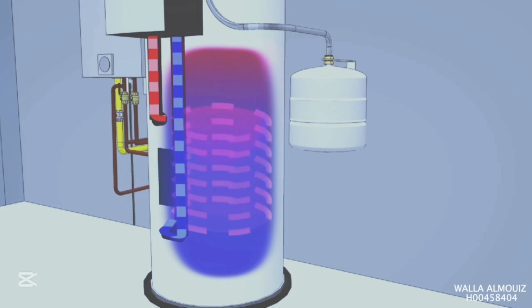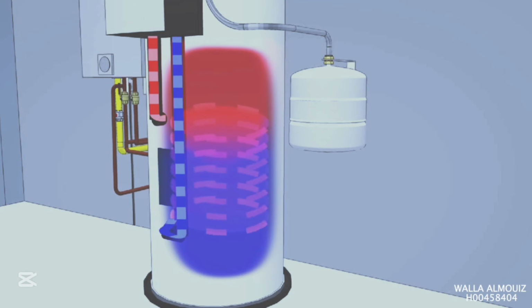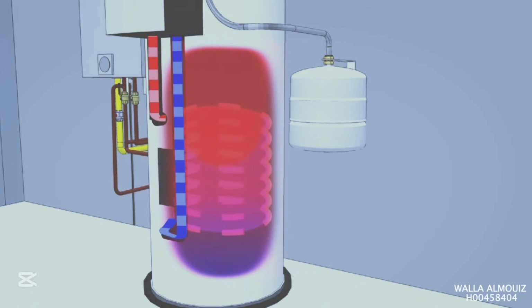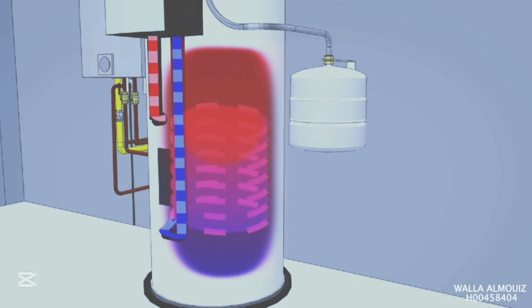This is how heat is transferred from the solar heated fluid to the university's water supply. Once the hot water tank reaches its maximum temperature set point, the solar differential controller turns the pump off until the tank temperature drops again. This cycle continues for as long as solar energy is available.